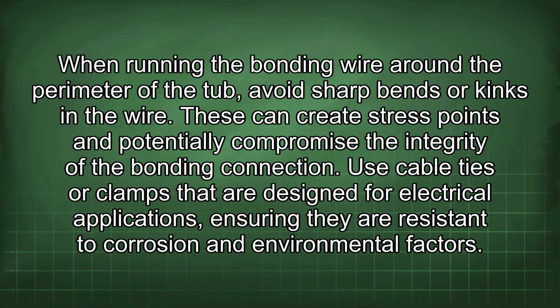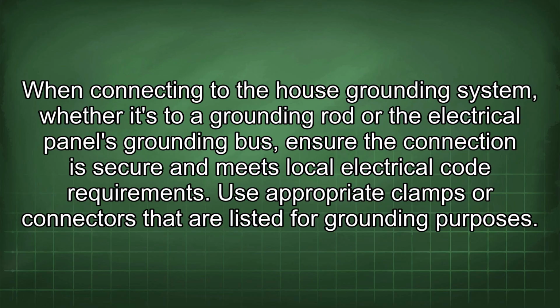Use cable ties or clamps that are designed for electrical applications, ensuring they are resistant to corrosion and environmental factors. When connecting to the house grounding system, whether it's to a grounding rod or the electrical panel's grounding bus, ensure the connection is secure and meets local electrical code requirements. Use appropriate clamps or connectors that are listed for grounding purposes.